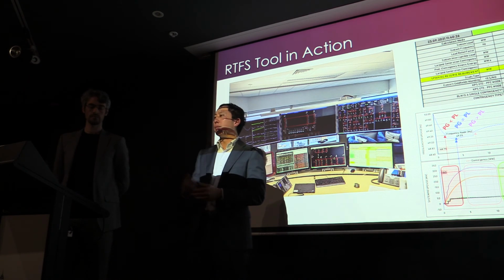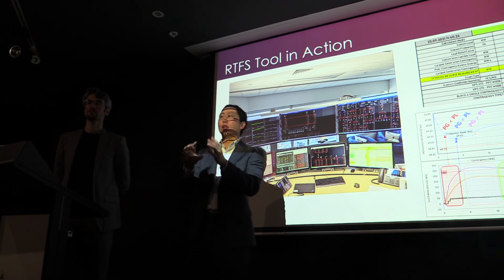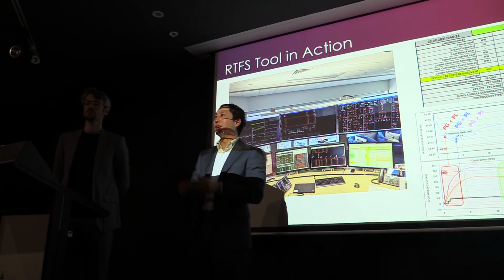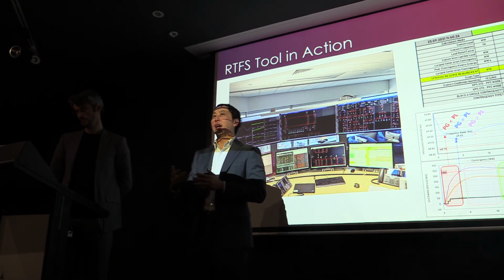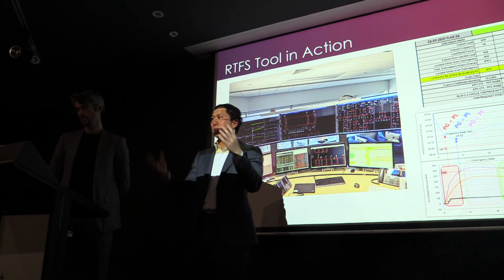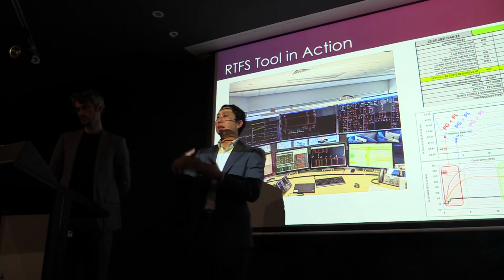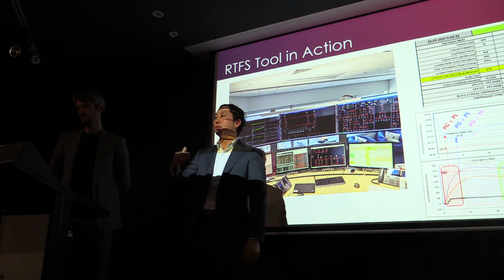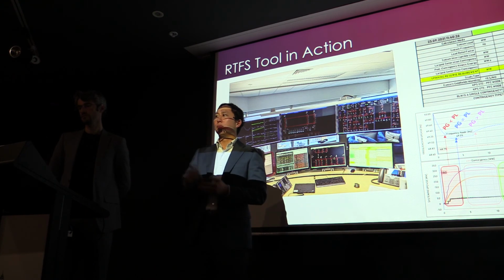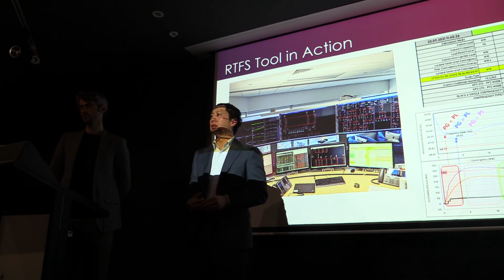In fact, a lot of these grid forming inverters have what's called virtual synchronous machine mode. So they have controls that look a lot like a synchronous generator, and provide inertia in a very similar way. It's almost like a swing equation inside their controller. And yes, so they can provide it. Now, the limitation is actually on power electronics, because whereas a real synchronous machine is just a heavy piece of metal spinning around, now you're actually limited by your converter, your IGBT transistors, because you can only give out so much current. So you're probably limited on how much inertia you could get from one of these virtual inertia machines.